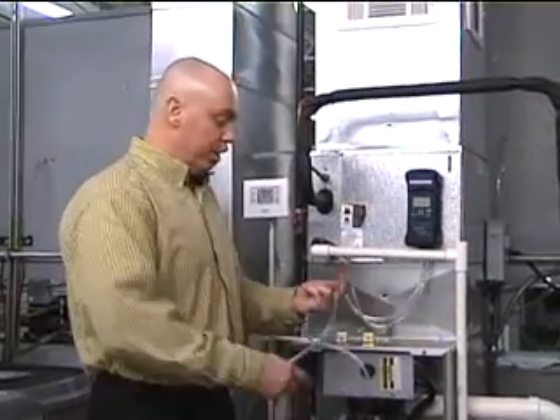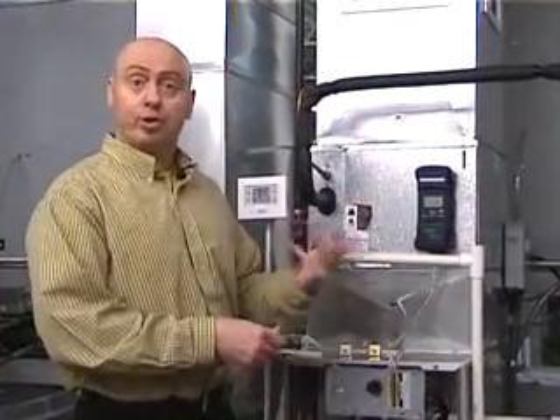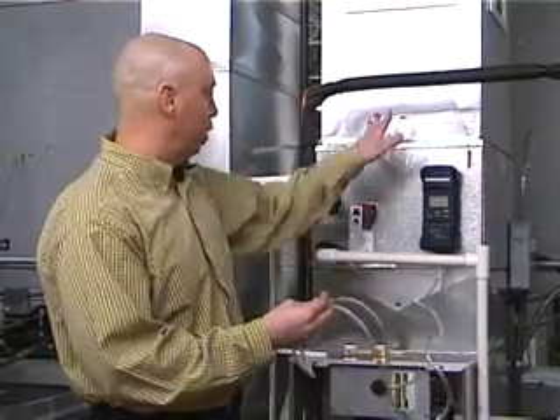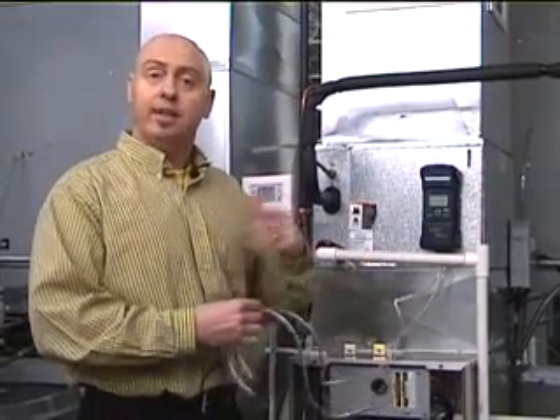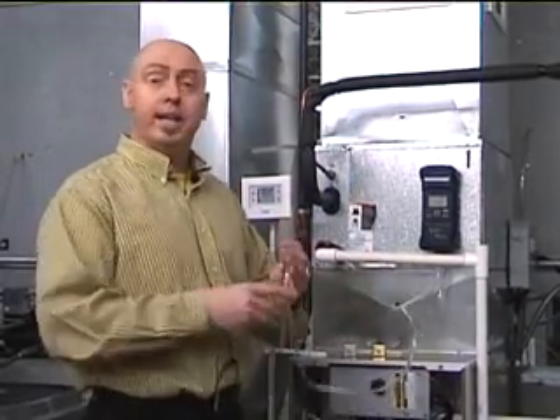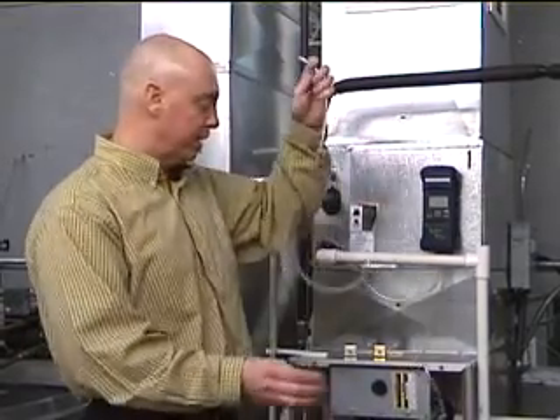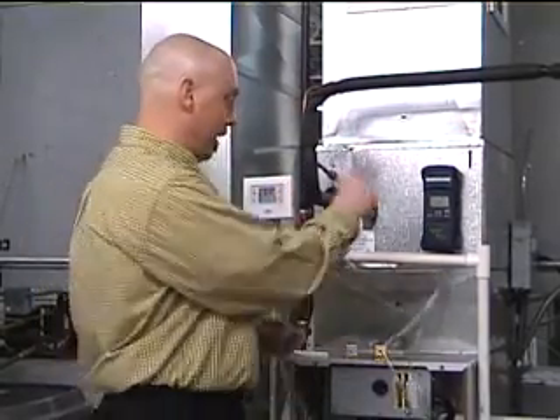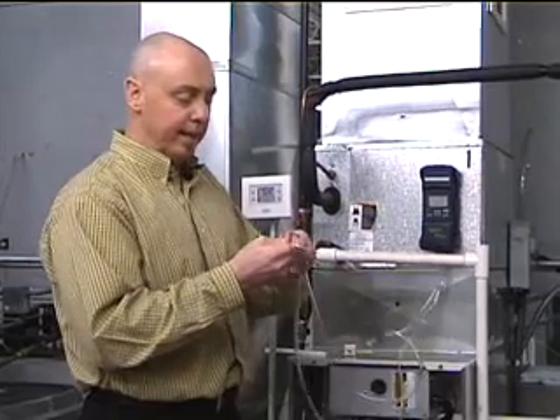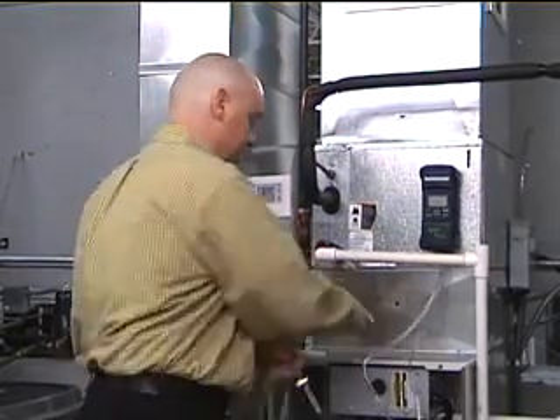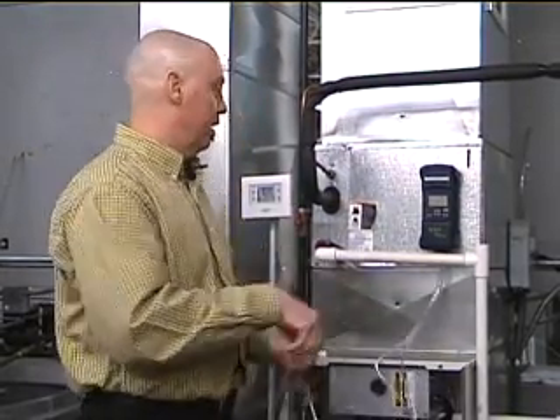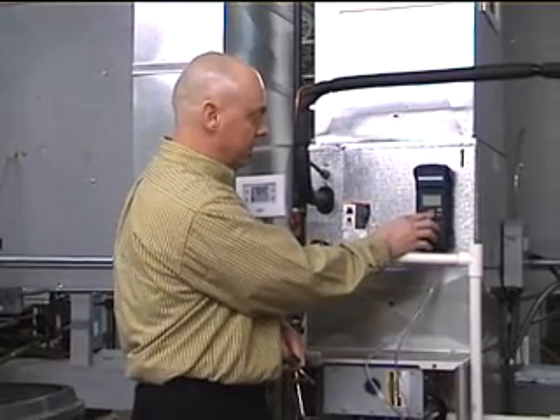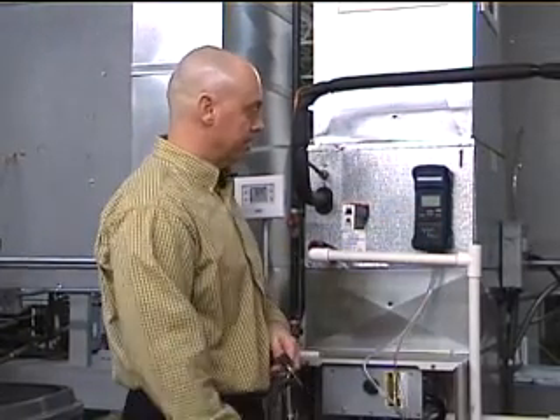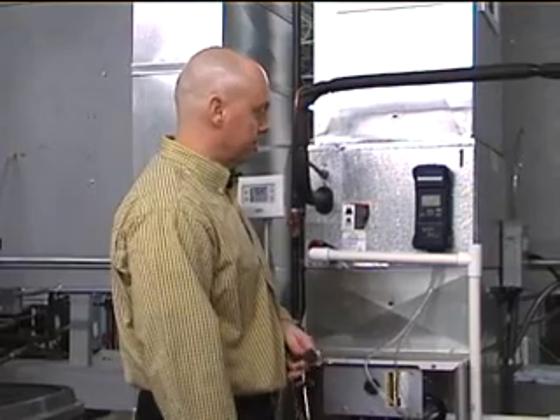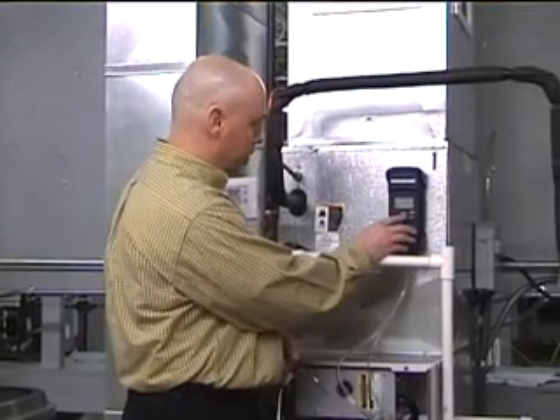One thing I wanted to show you real quick as we start winding down here is, you can check your total static pressure, but since you have a couple holes here across the coil, I can tell you what the pressure drop across the coil is too, and it's pretty easy to do. Again, I do it almost the same way. I take the two hoses off my meter, I attach my static probes, I zero the meter out by scrolling down, hitting enter. Do that one more time.